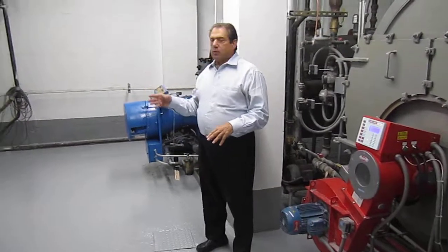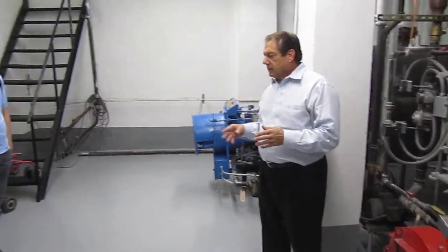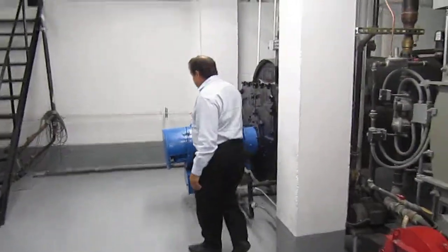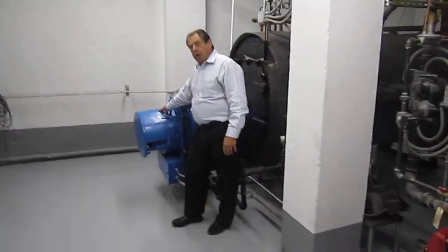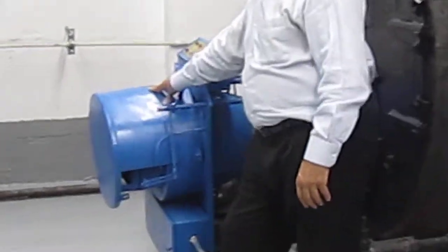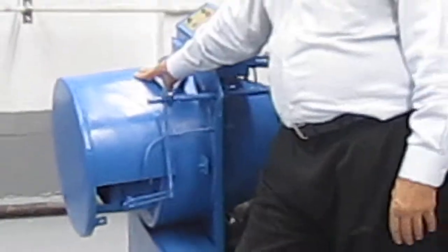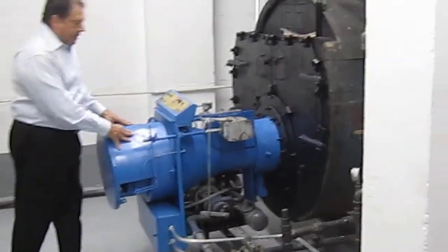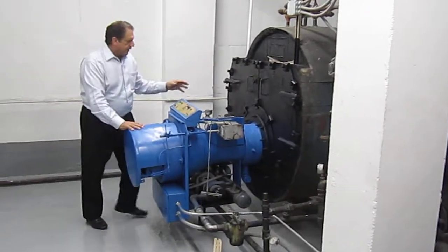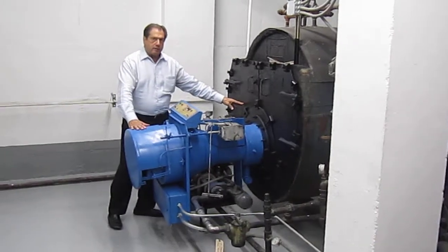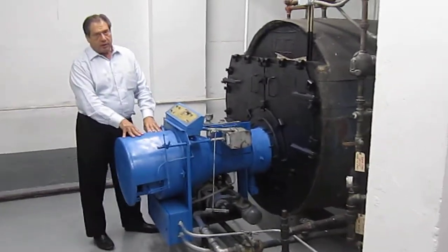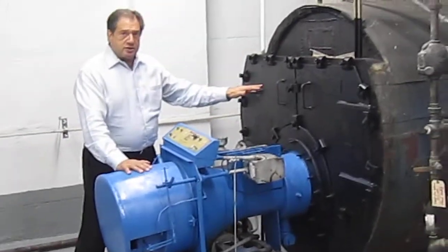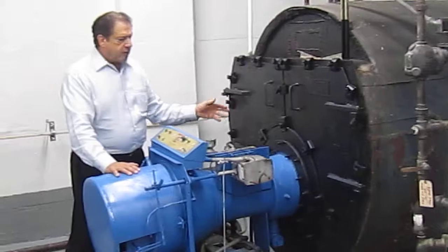Okay, there's some questions that I'd like to continue to answer. First of all, I was asked, what is this part of the boiler do? And I want to explain that this is a fan in here. And the fan, when the oil ignites, the fan motor blows the flame into the chamber that we talked about earlier. So without this fan motor, if this doesn't work properly, the fire would never reach into the cylinder or the chamber and burn correctly.